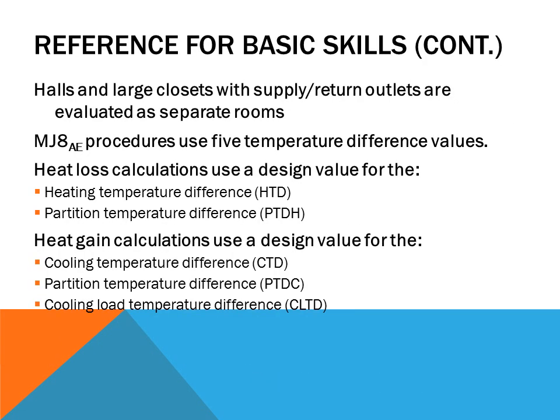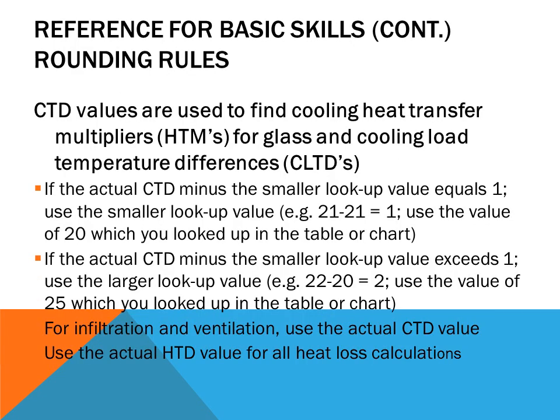And then again, like I said, heat loss calculations are used for design values, but also heat gain calculations are used for design values. And this is how it's listed out in the Manual J. So cooling temperature difference values are used to find cooling and heat transfer multipliers. It's multiplying those numbers together to come up with BTUs, or heat gains through the structure. So just take a look at these bullet points as you go through, and I'll work you through examples of how to determine these things.